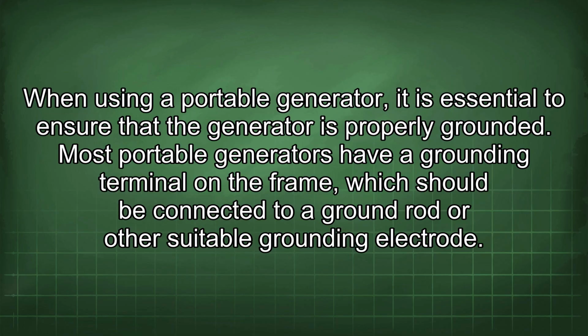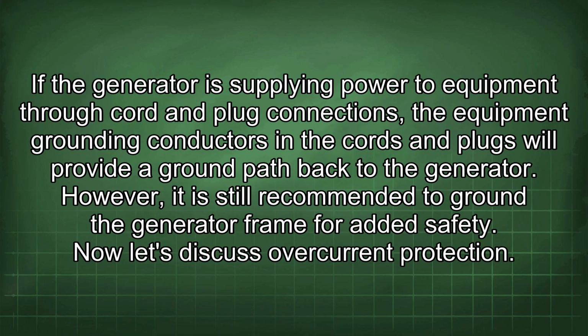When using a portable generator, it is essential to ensure that the generator is properly grounded. Most portable generators have a grounding terminal on the frame, which should be connected to a ground rod or other suitable grounding electrode. If the generator is supplying power to equipment through cord and plug connections, the equipment grounding conductors in the cords and plugs will provide a ground path back to the generator. However, it is still recommended to ground the generator frame for added safety. Now let's discuss overcurrent protection.